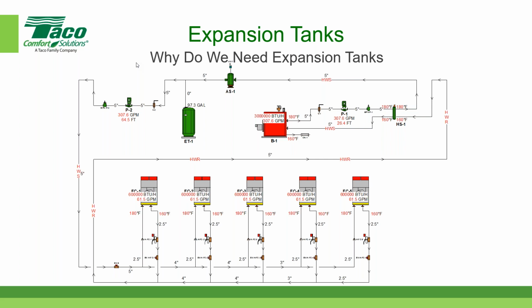So in a chilling plant, is the expansion in the evaporator side or condenser side? It's on the evaporator side, because the evaporator typically is a closed loop pressurized system. On the condenser water side, it could be closed loop pressurized if you were going to a closed circuit cooling tower. But if you're going to a more common cooling tower for a condenser water system, the cooling tower would be open to the atmosphere and you would not use an expansion tank, because as the fluid expands, it would simply go up and down inside the basin of the cooling tower. The water level inside the cooling tower would go up and down as a function of expansion.